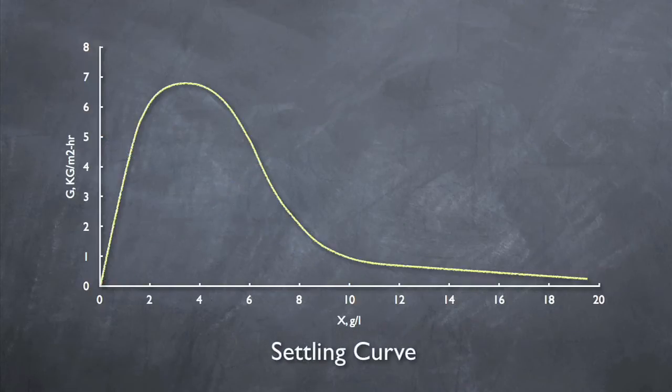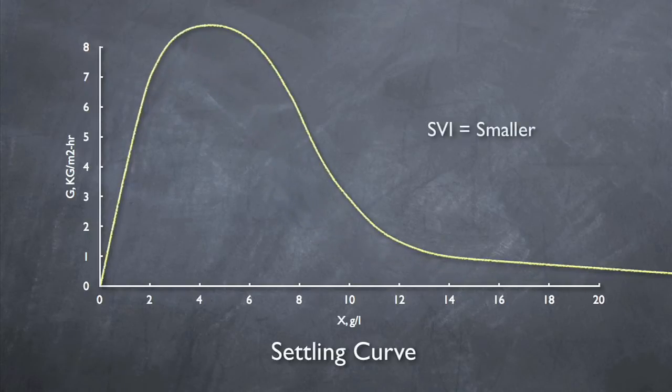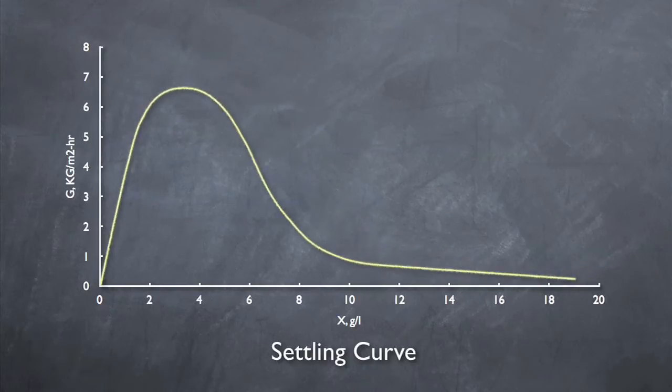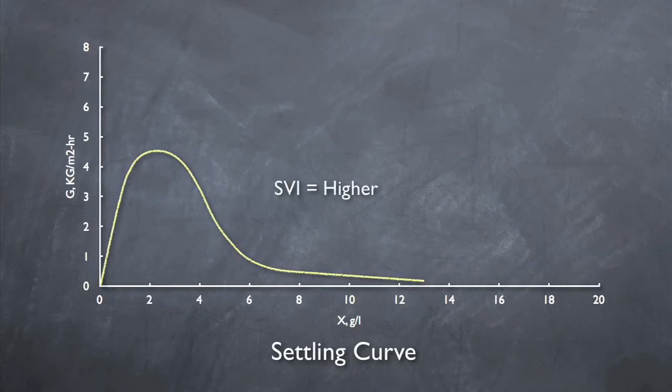The first component is the settling curve. This curve is developed by performing velocity settling tests at various concentrations of mixed liquor on site. However, empirical equations based on the sludge volume index, SVI, have been developed and are plenty accurate for using and deriving this curve. A smaller SVI, which represents faster settling, results in a larger settling curve. A higher SVI, which represents slower settling, results in a smaller settling curve.